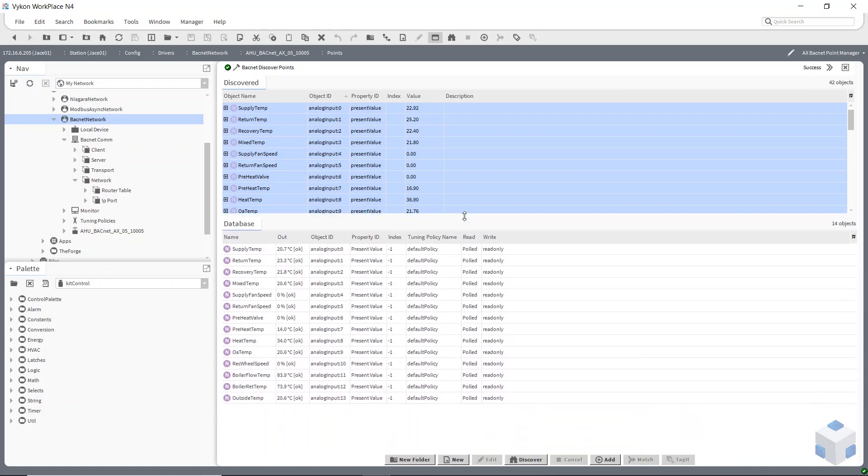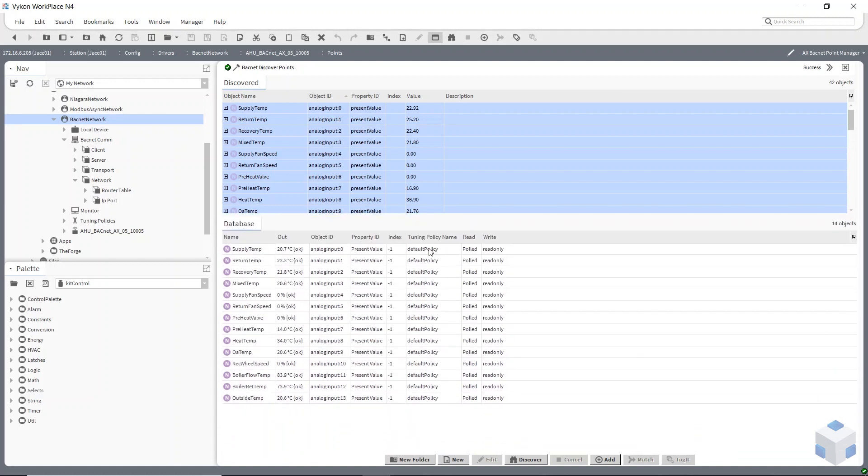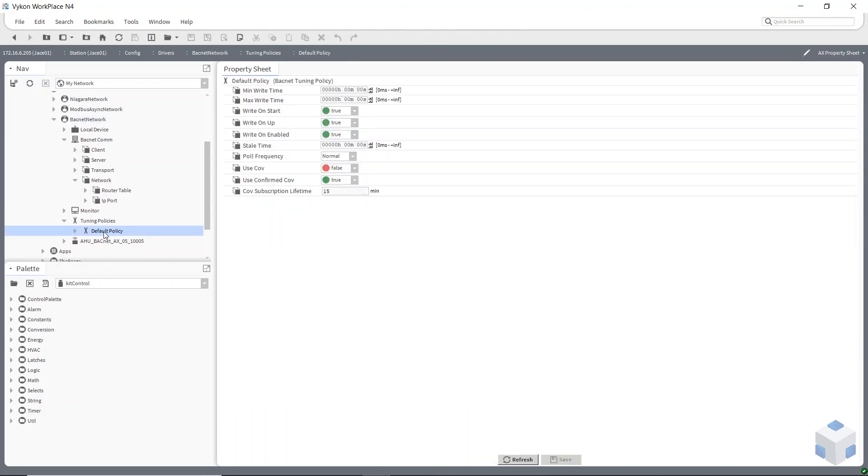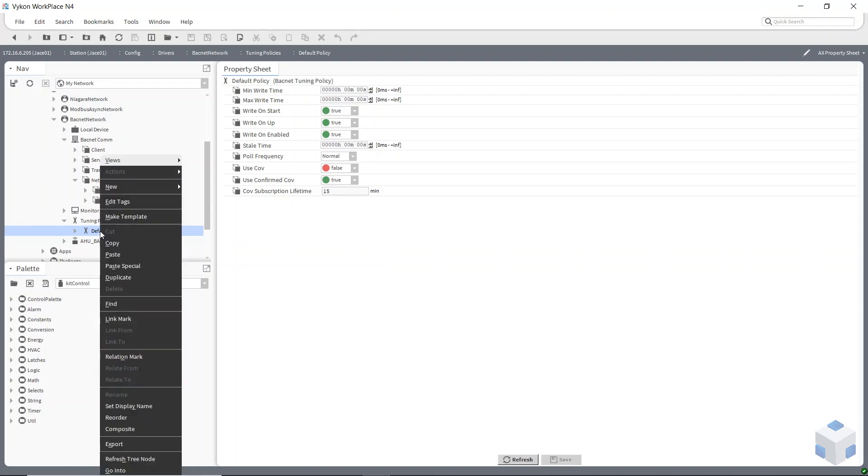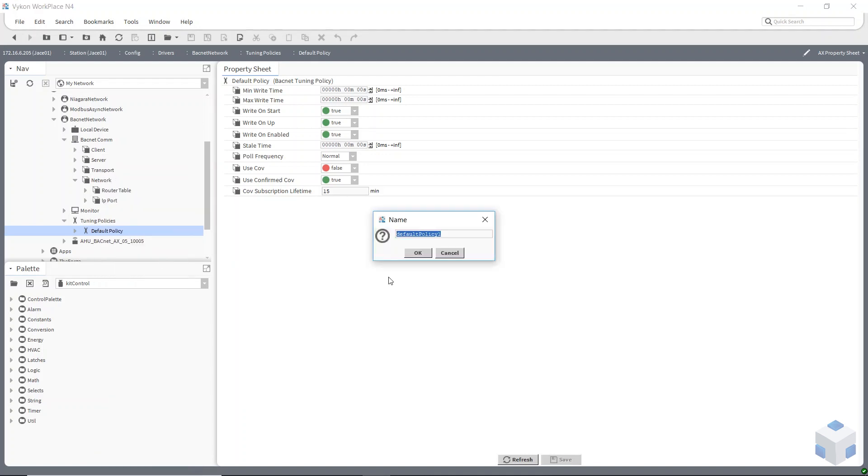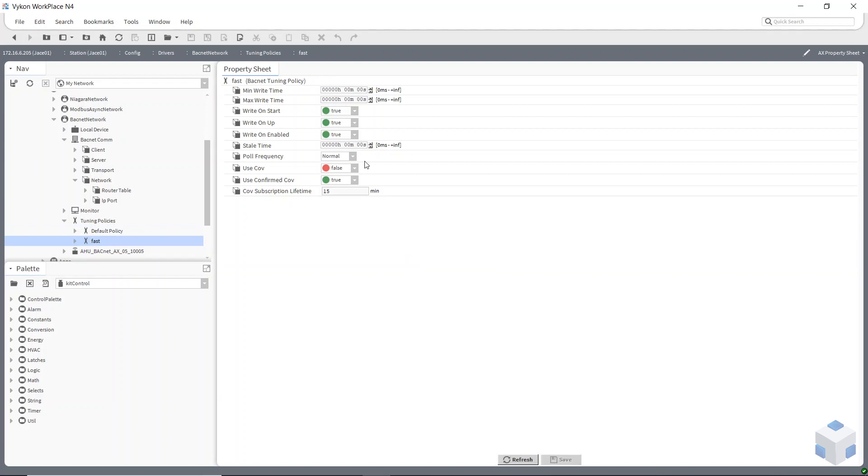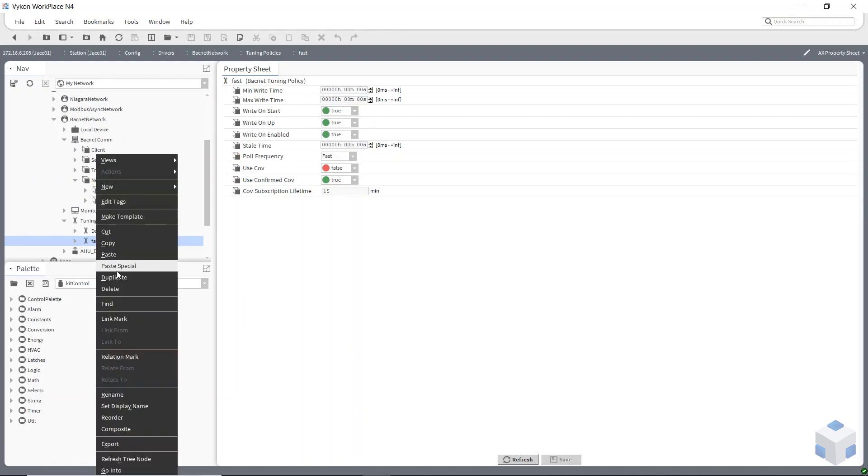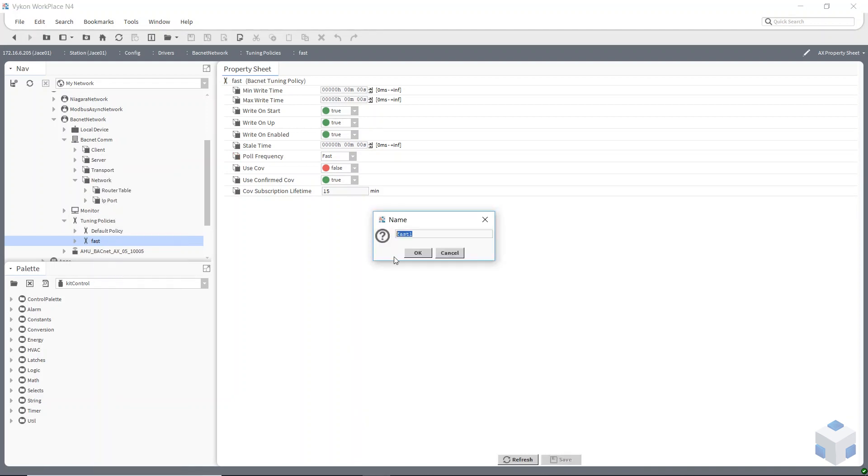So if you look down on my database everything's used the default policy at the moment so you can change that or you can add your own policies. So if you look further down in your BACnet network there's a tuning policy in the sidebar. If you unfold that the default policy, if we have a look that's how it's set up by default, so you can change that or you can just create your own policies. So just duplicate it, give it a new name. Okay so I can double click on that and edit that now, change this to fast, save that. Add another one, just duplicate it again, call this one slow.